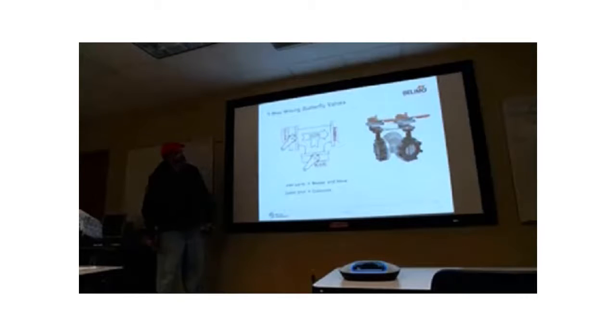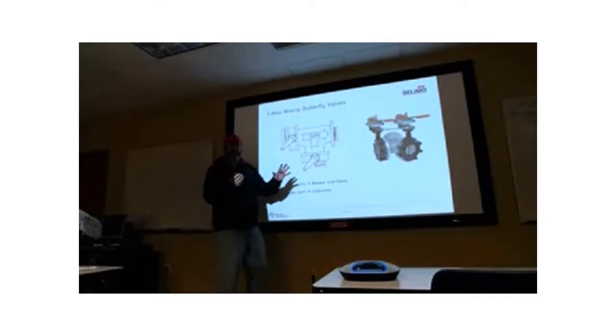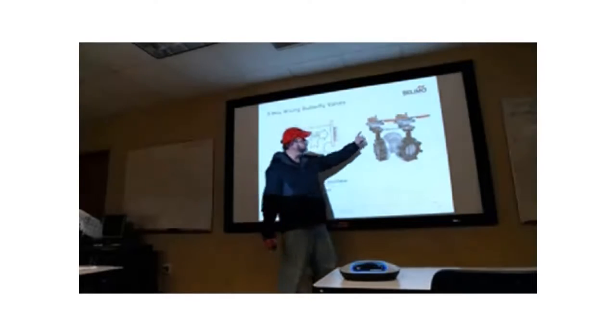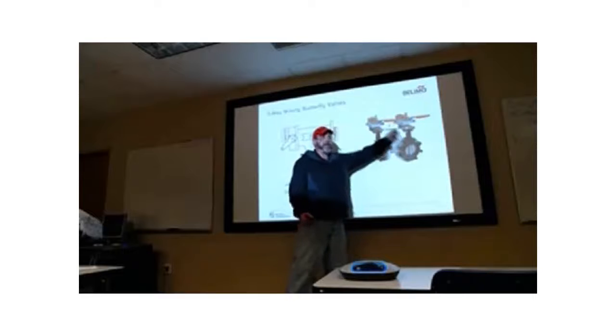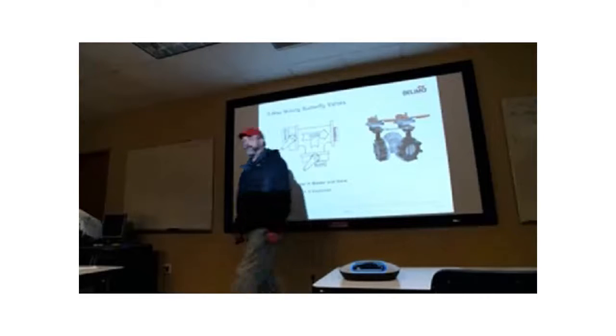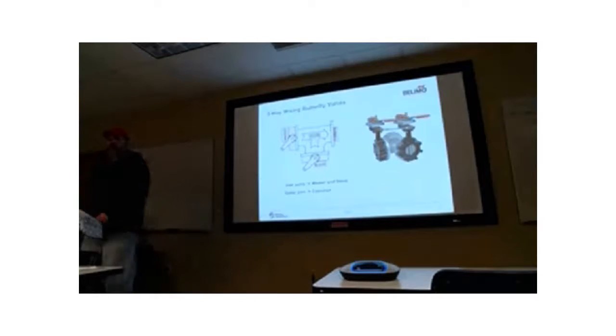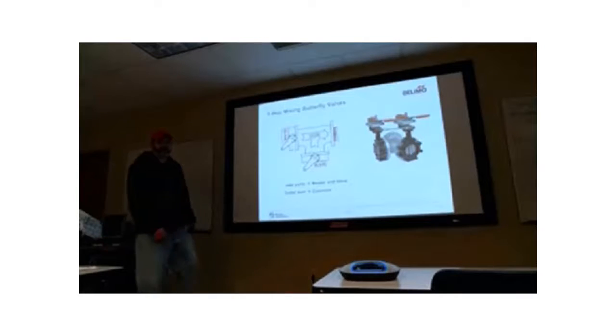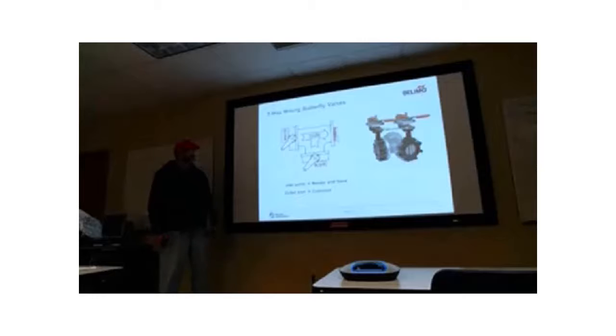There. Now back to, remember we talked about the master slave thing on the air side? What did I say about that? We need a special type of actuator. It's called an MFT, a programmable actuator. Well, these are MFTs, right? Because they're mechanically linked, right? So if you see a butterfly valve with two actuators on it, those are going to be those programmable MFT actuators, and they need to be. You can't replace them with just a plain vanilla actuator.